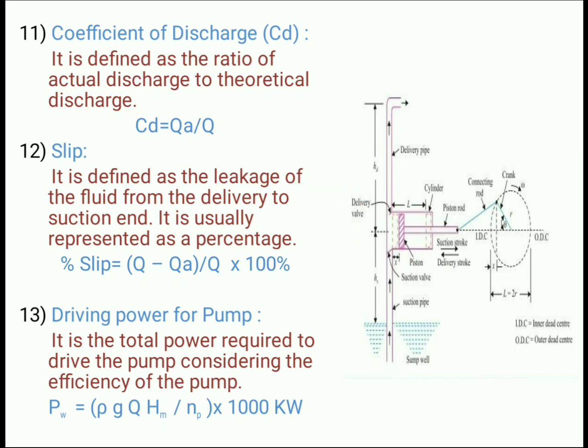So this leakage has to be considered while calculating the discharge. To consider the amount of leakage, we can find out the slip percentage, that is, theoretical discharge minus actual discharge upon theoretical discharge.